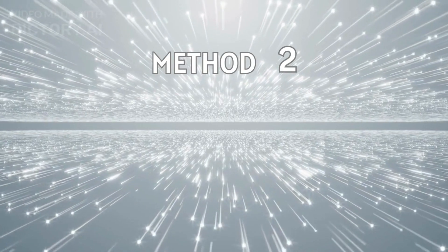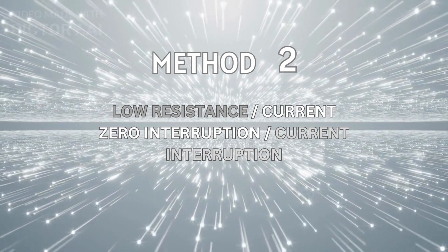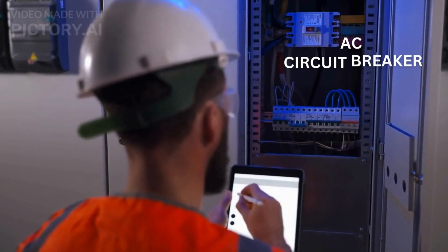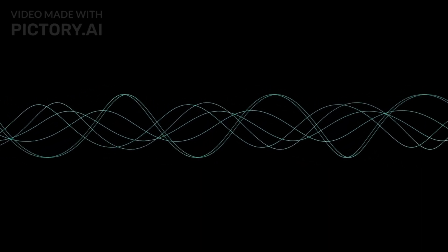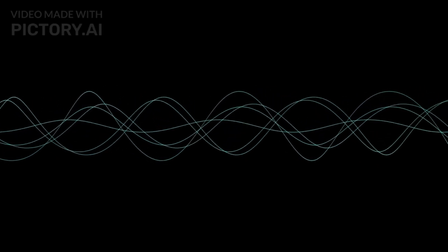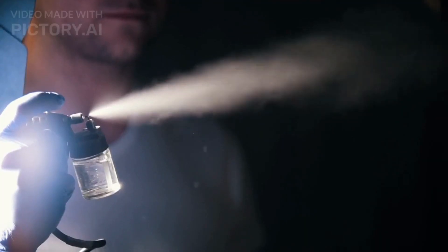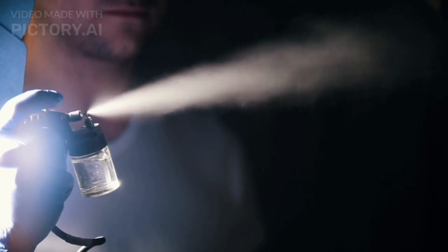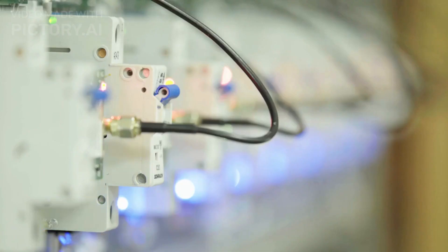The second method of arc interruption is the low resistance or current zero interruption method, used for AC circuit breakers. The alternating current of 50 Hz frequency crosses zero 100 times per second. At every zero crossing, the arc current is zero and is again established. Thus the arc restrikes when the current is near zero crossing. A dielectric medium — in the form of air, SF6 gas, etc. — is introduced near the contacts, causing de-ionization and extinguishing the arc. The current zero instant is determined by using a suitable electronic circuit.